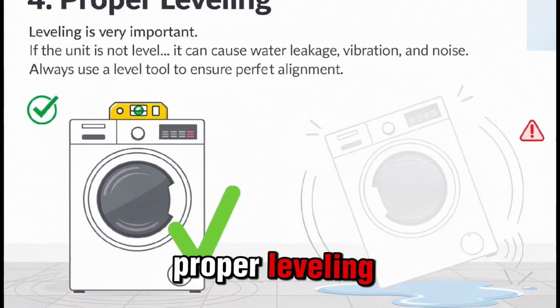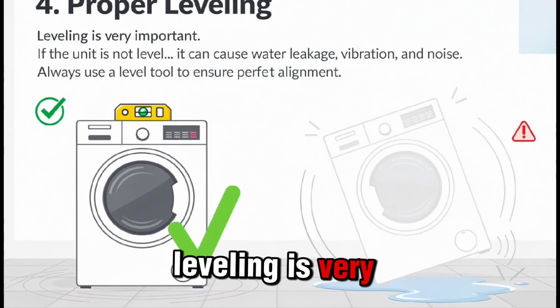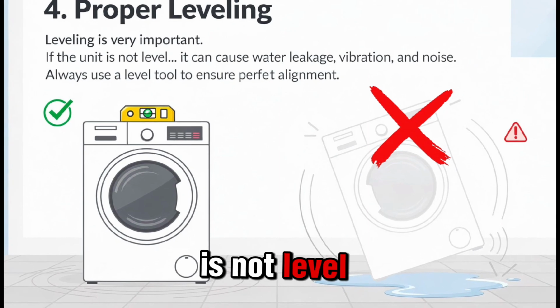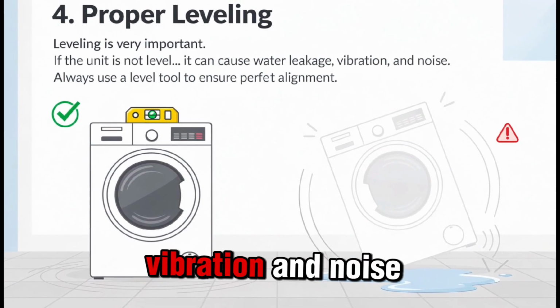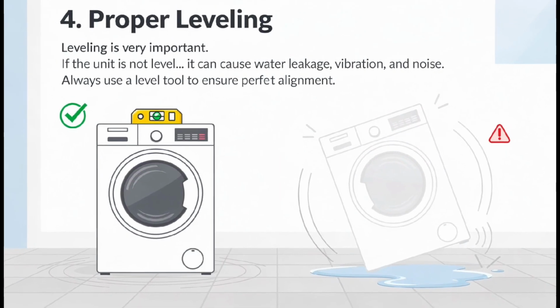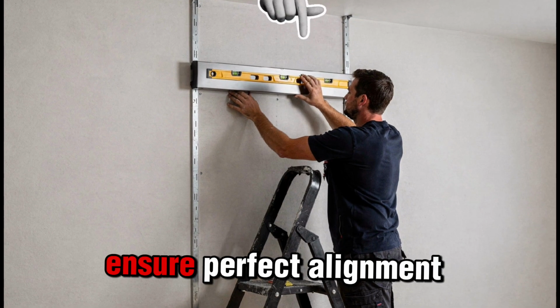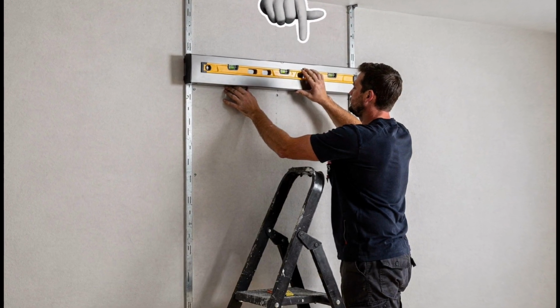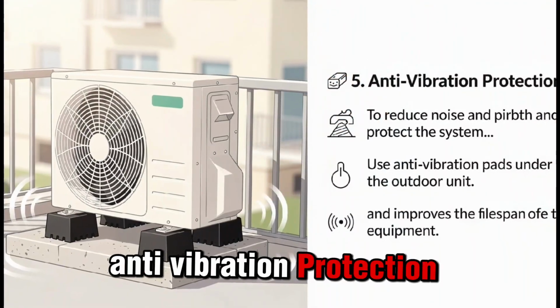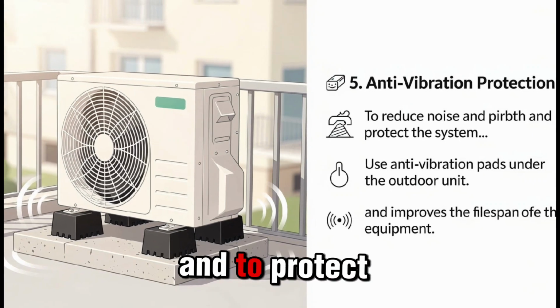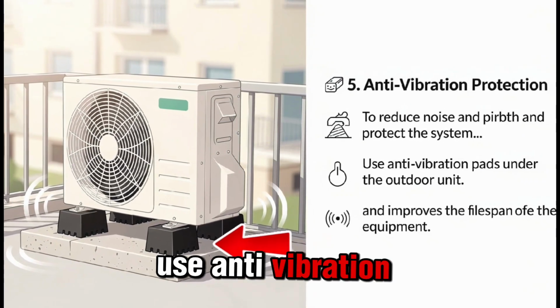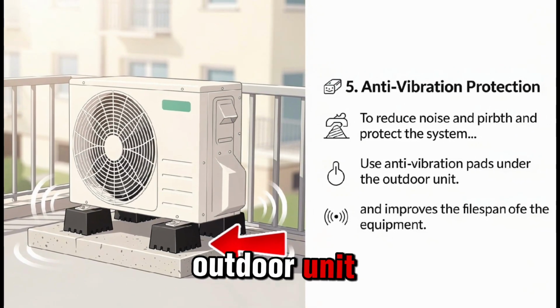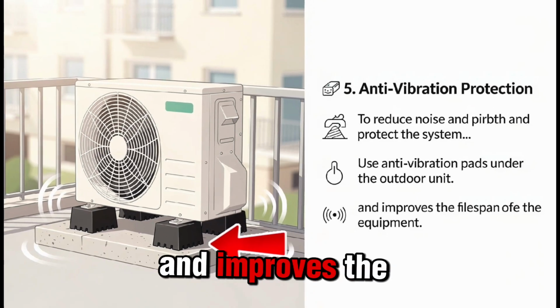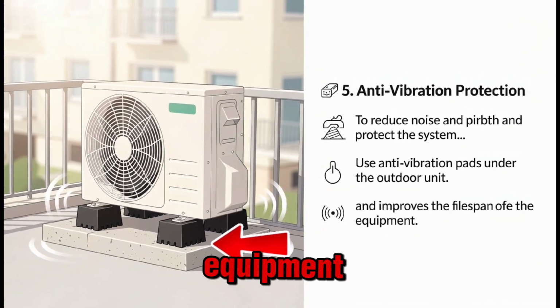Proper leveling. Leveling is very important. If the unit is not level, it can cause water leakage, vibration, and noise. Always use a level tool to ensure perfect alignment. Anti-vibration protection. To reduce noise and protect the system, use anti-vibration pads under the outdoor unit. This increases comfort and improves the lifespan of the equipment.